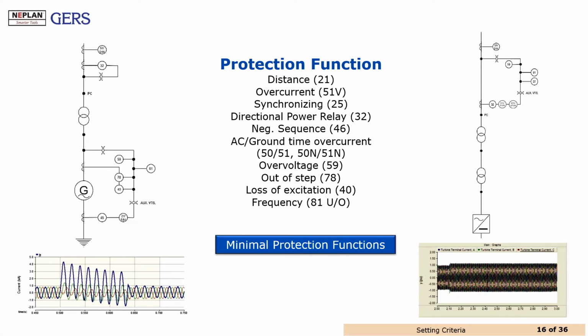This slide is showing that for these kinds of generation systems, we have minimum required protection functionalities. For example, synchronous generators have to be supported by out-of-step relays and loss-of-excitation relays, but we can see that they are not required in this kind of protection. On this side, for the inverter-based resources, we have some protections like the directional power relays, the overcurrent protections, the overvoltage, the frequency relays, the undervoltage relays, among other functionalities that we are able to implement as the minimal requirements on these protection systems.